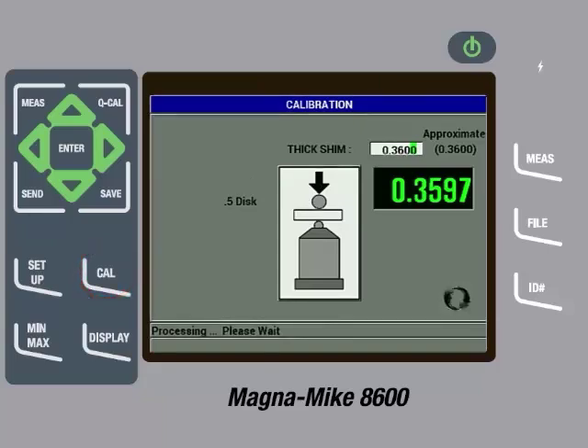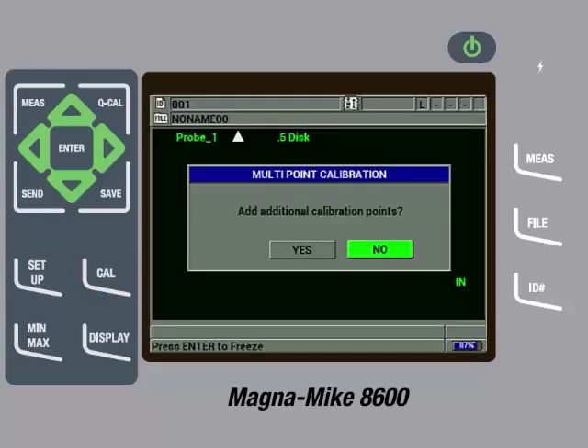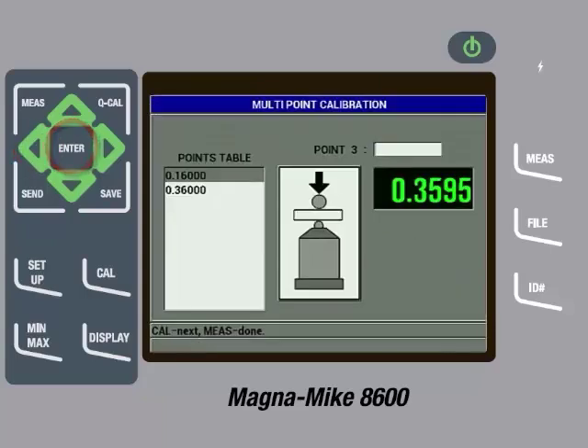After processing, the gauge will then ask if we want to add additional calibration points. If we choose no, the calibration process is over and we have completed a basic calibration. The recommendation is to always add additional calibration points since it improves measurement accuracy. Therefore, we will press the left arrow to highlight yes, and then press the Enter key.